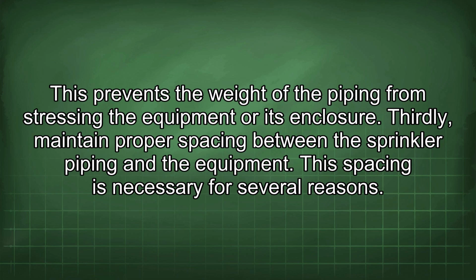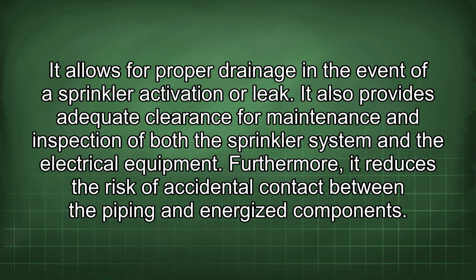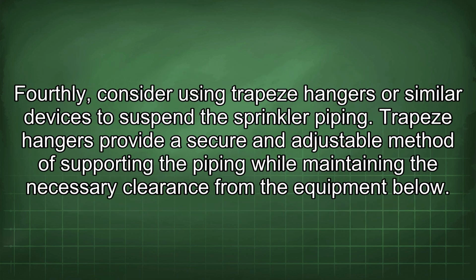Thirdly, maintain proper spacing between the sprinkler piping and the equipment. This spacing is necessary for several reasons. It allows for proper drainage in the event of a sprinkler activation or leak. It also provides adequate clearance for maintenance and inspection of both the sprinkler system and the electrical equipment. Furthermore, it reduces the risk of accidental contact between the piping and energized components. Fourthly, consider using trapeze hangers or similar devices to suspend the sprinkler piping. Trapeze hangers provide a secure and adjustable method of supporting the piping while maintaining the necessary clearance from the equipment below.